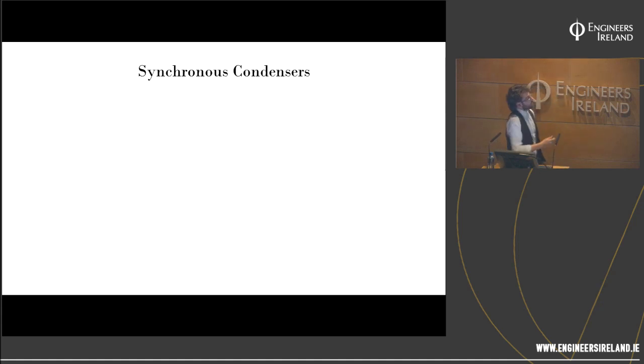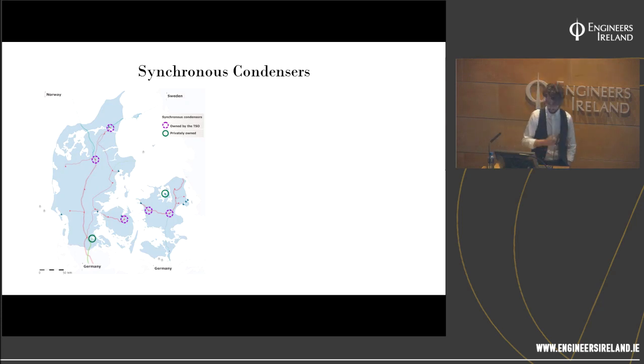Now, the leaders in synchronous condensers are EnergiNet in Denmark. The purple dots there are the TSO-owned synchronous condensers, and the green ones are independents. And the reason this came about was because the Nordic market sets the generator dispatches. But what was happening was there wasn't enough controllability on the system to maintain your voltages. So what the operator had to do was go out of the market, go out of merit, and ask a generator to turn on so that it could provide ancillary services.